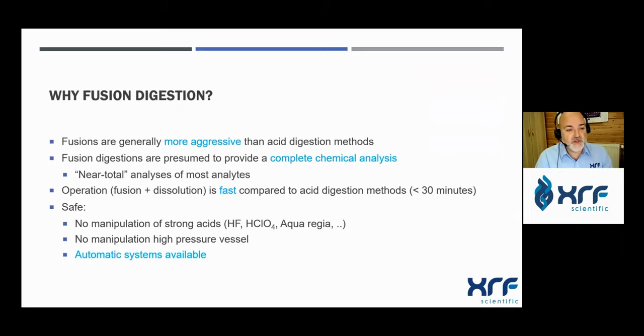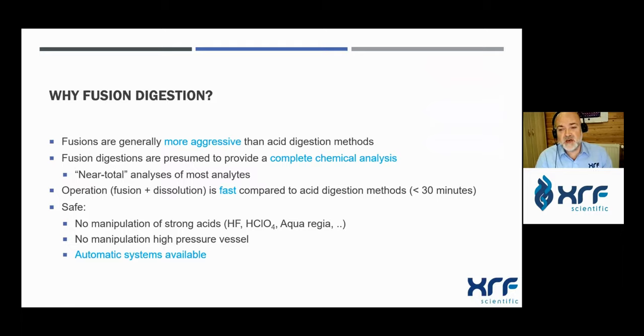Fusion digestion is generally more aggressive than acid digestion and provides a complete chemical analysis — what we call near-total analysis of most analytes. The operation — fusion plus dissolution — is fast compared to some acid digestions, typically below 30 minutes. It is also safer because there is no manipulation of strong acids requiring specific environments like perchloric or hydrofluoric acid, no use of high pressure vessels, and the complete sample preparation can be automated.